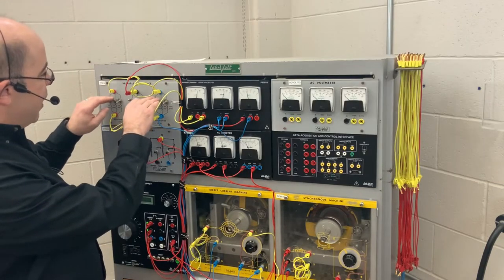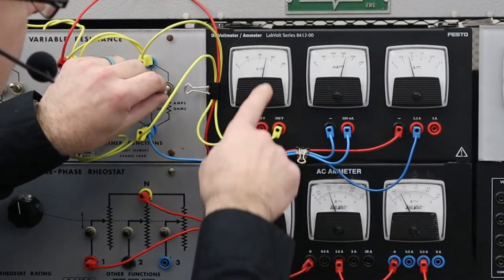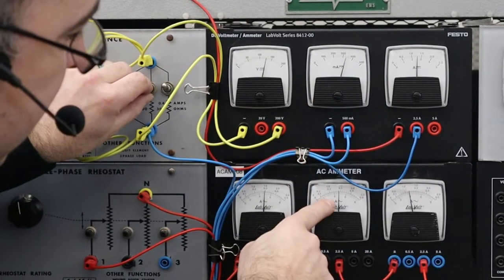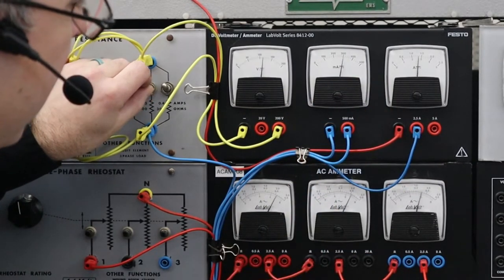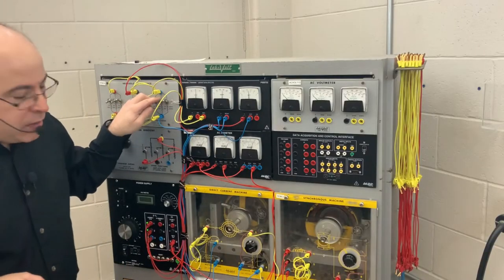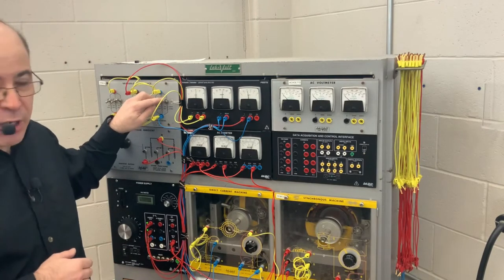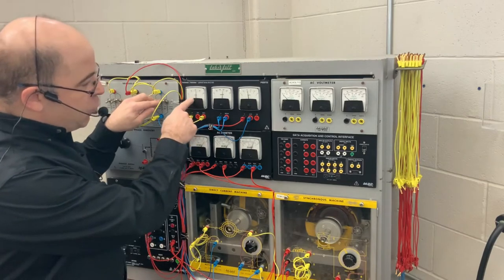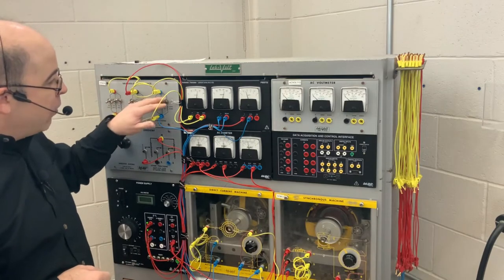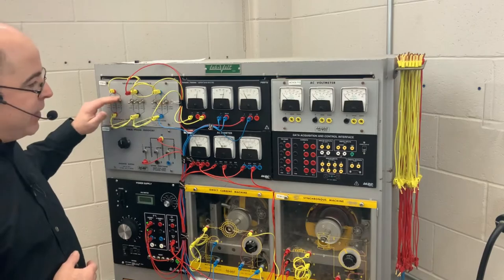Now I'm going to turn these off, and we can see the currents coming up. Right here it becomes the breaking point — this is the concept of counter torque. The machine is drawing more voltage and current than the synchronous motor can provide in horsepower. The only way to fix this is to back off some of the resistance.